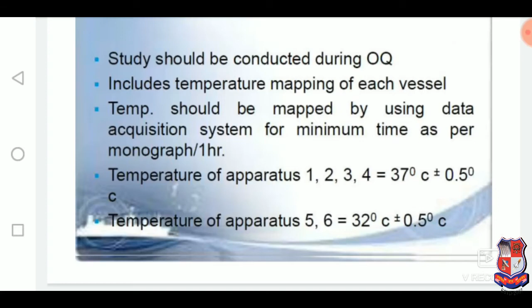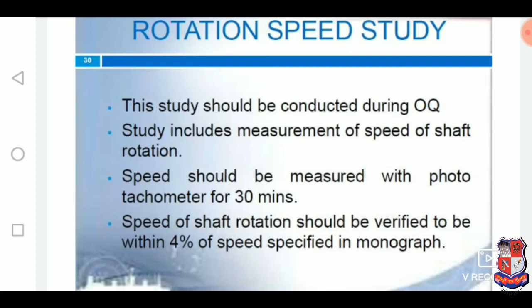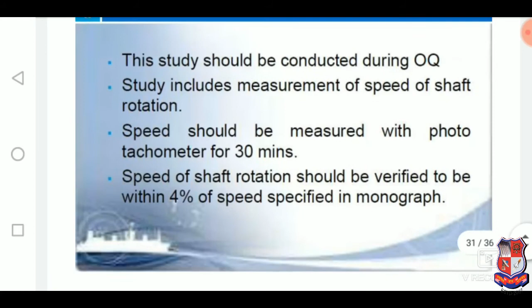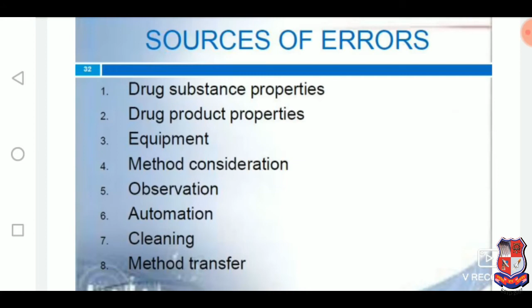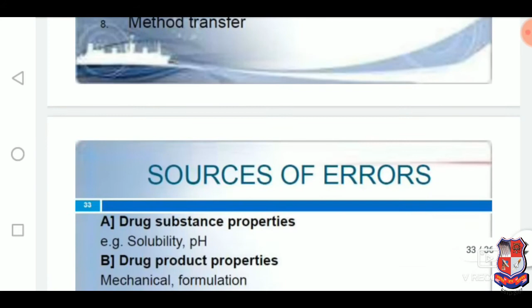Rotation speed study. This study should be conducted during the operation qualification. The study includes the measurement of speed of shaft rotation. Speed should be measured with a phototachometer for 30 minutes. Speed of shaft rotation should be verified to be within 4% of the specified limit in the monograph. So sources of error should also be considered. What are the sources of error? The first ones are drug substance property, drug product property, equipment, method consideration, observation, automation, cleaning, and method transfer.